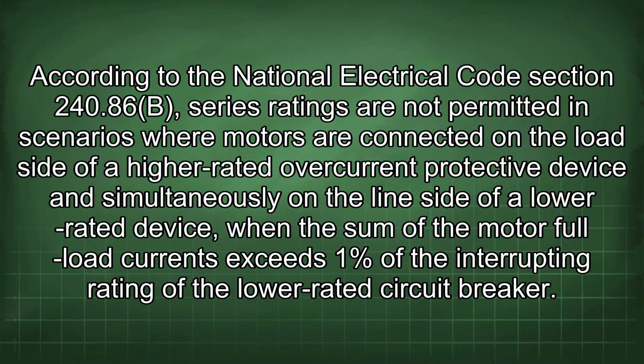According to the National Electrical Code Section 240.86(B), series ratings are not permitted in scenarios where motors are connected on the load side of a higher rated overcurrent protective device and simultaneously on the line side of a lower rated device when the sum of the motor full load currents exceeds 1% of the interrupting rating of the lower rated circuit breaker.